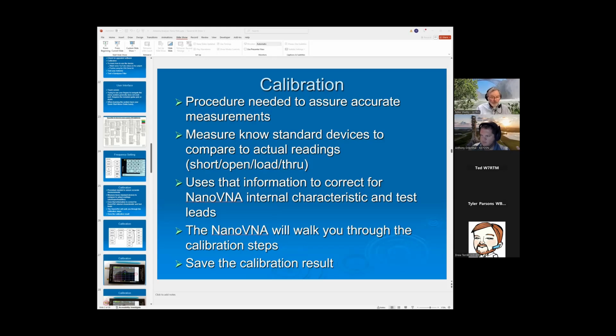So it uses that information to correct any internal characteristics that aren't quite right and corrects that for your testing. The Nano VNA will walk you through the calibration step, but the key thing is once you get finished with that, you need to make sure that you save that calibration.